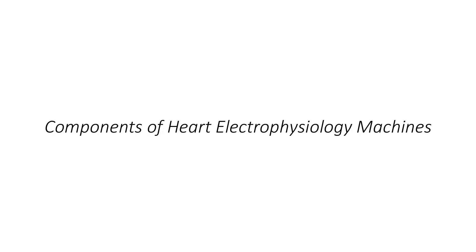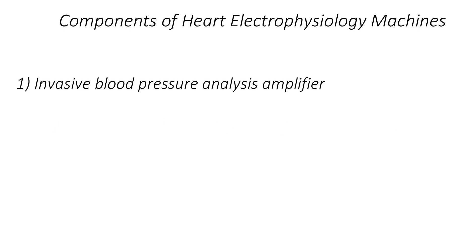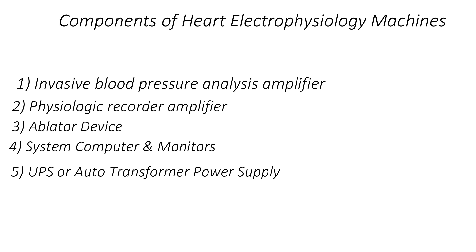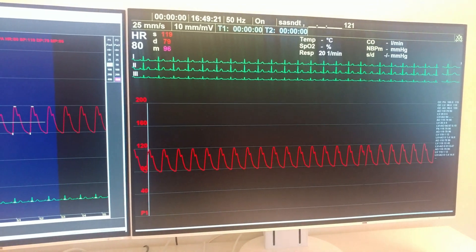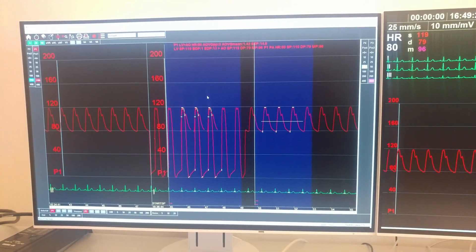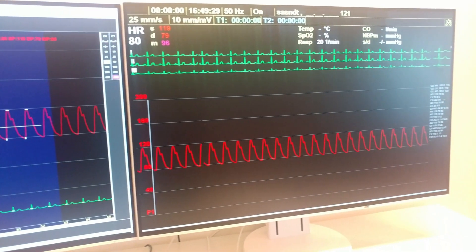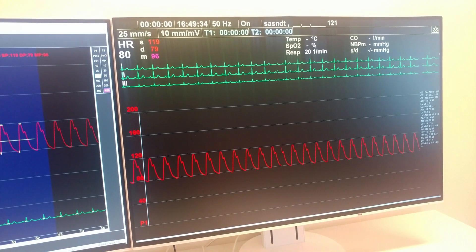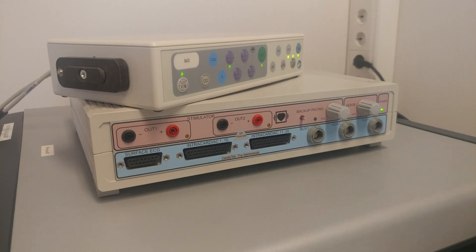Components of heart electrophysiology machines include an invasive blood pressure analysis amplifier, a physiologic recorder amplifier with stimulator and cardiac output, an ablator device, system computer and monitors. Some suppliers also provide an auto transformer or UPS supply along with the devices. The blood pressure analysis amplifier is used to measure multiple site invasive blood pressures to analyze variation and know time differences. The process of recording signals from various electrode catheters is accomplished by means of a data acquisition system or physiologic recorder.